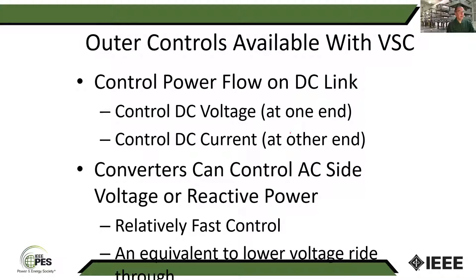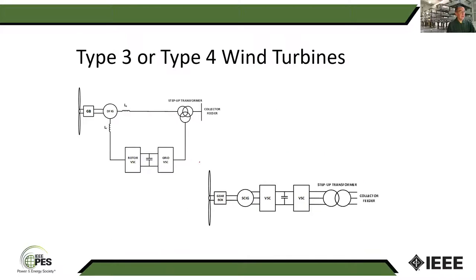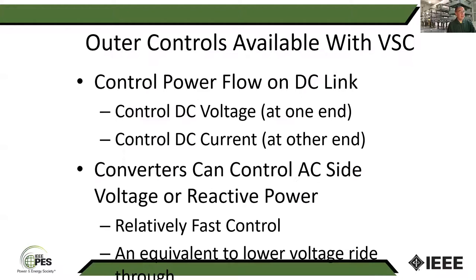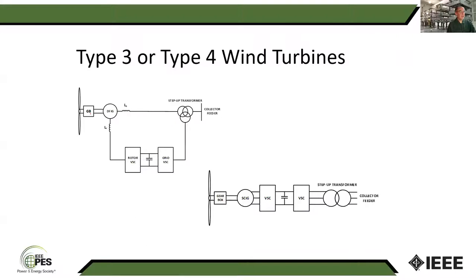And then you can have outer controls, and sorry about this one, it got a little bit big, I should have had the font smaller. You could control DC voltage, you could control DC current, you can control AC voltage or AC reactive power. And so when you see some applications for renewable generation, if we look at a type 3 wind turbine, so this is a doubly fed induction generator, we have the circuit connected to the rotor. And what this allows is that by putting this circuit here, you can control the effective frequency of the rotor flux. So even though the rotor itself may be turning slower than synchronous speed, which would mean for an induction machine that it's going to look like a motor, you can inject power through this and control the frequency of that.